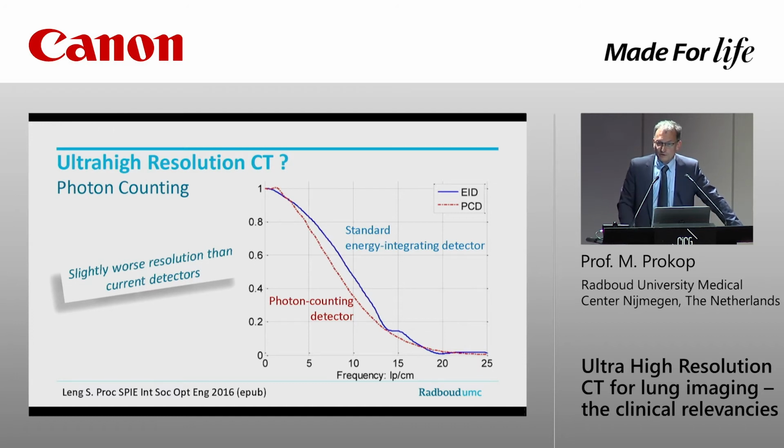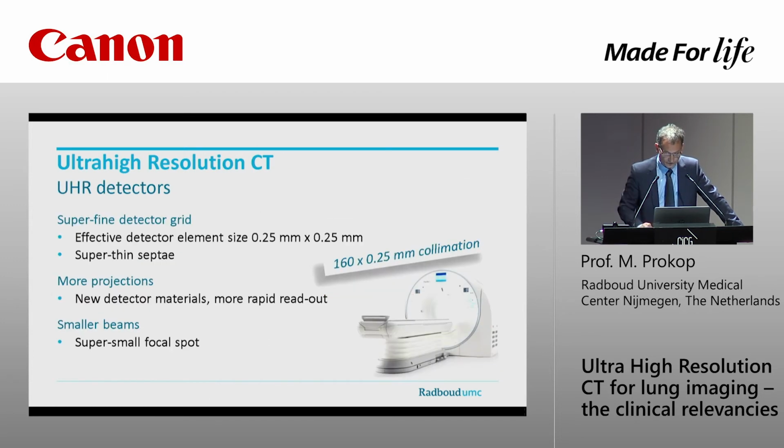If you look at the spatial resolution, however, the way it's implemented at the moment, a standard energy integrating detector is still slightly higher in resolution than a photon counting detector.